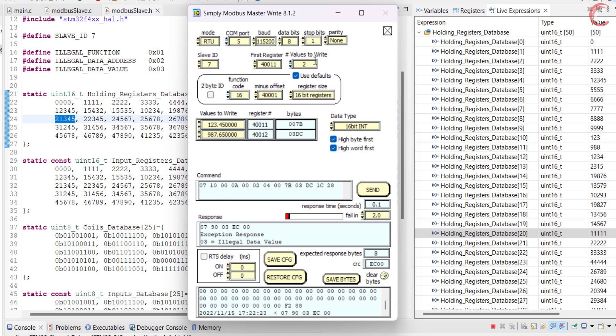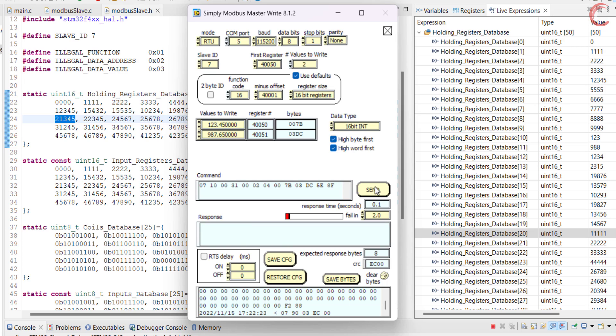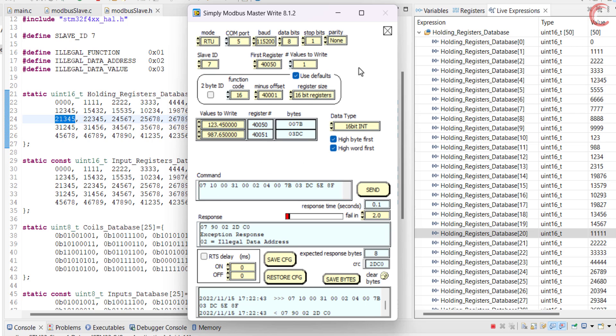Similarly, the database only contains 50 registers, so if the master wants to write more than that, the slave will send an exception saying illegal data address. Although it can write the 50th register, since it's defined in the database.